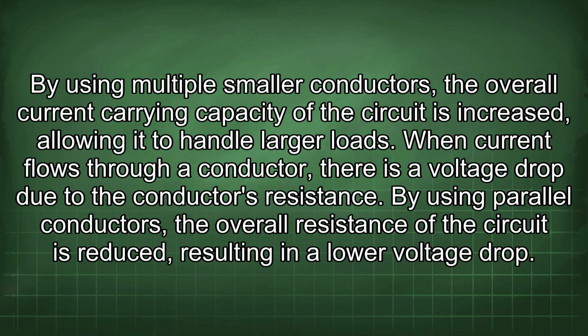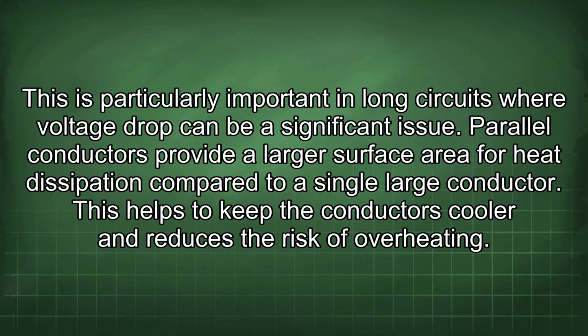When current flows through a conductor, there is a voltage drop due to the conductor's resistance. By using parallel conductors, the overall resistance of the circuit is reduced, resulting in a lower voltage drop. This is particularly important in long circuits where voltage drop can be a significant issue.